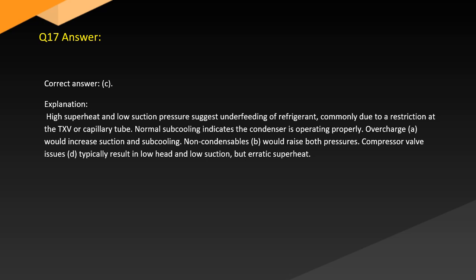Answer. Correct answer: C. Explanation. High superheat and low suction pressure suggest underfeeding of refrigerant, commonly due to a restriction at the TXV or capillary tube. Normal subcooling indicates the condenser is operating properly. Overcharge, A, would increase suction pressure and subcooling. Non-condensables, B, would raise both pressures. Compressor valve issues, D, typically result in low head and low suction but erratic superheat.